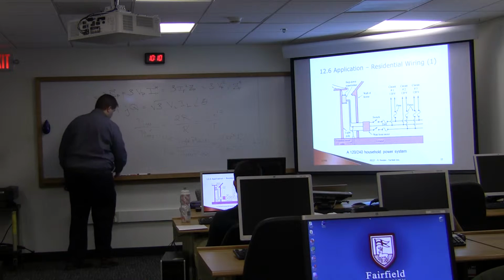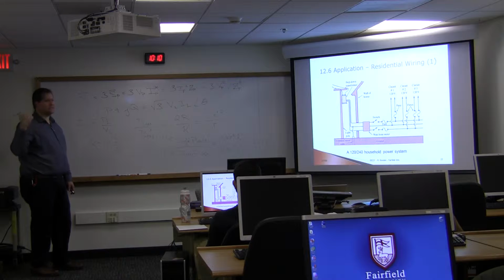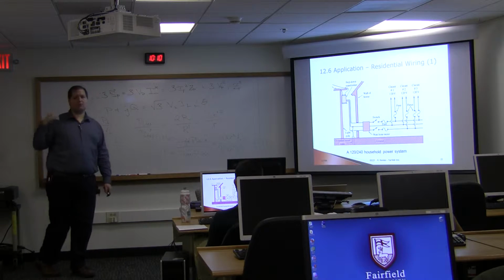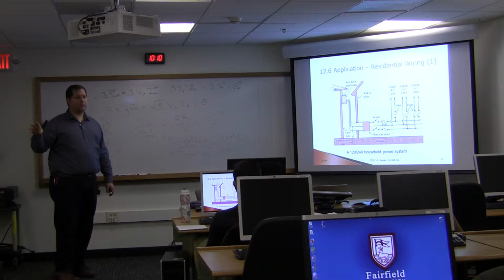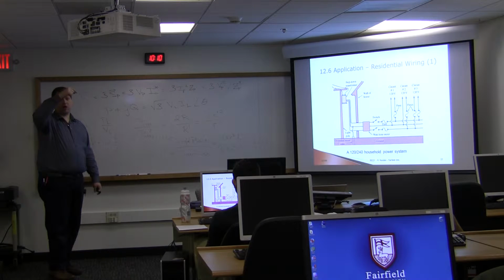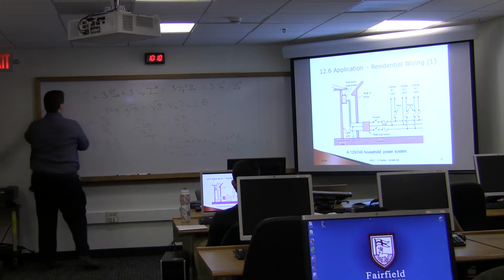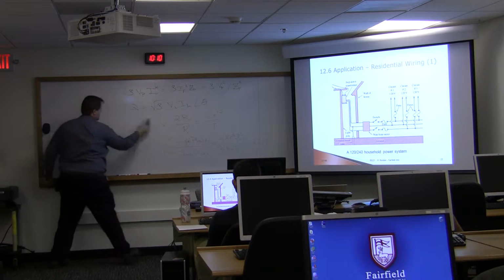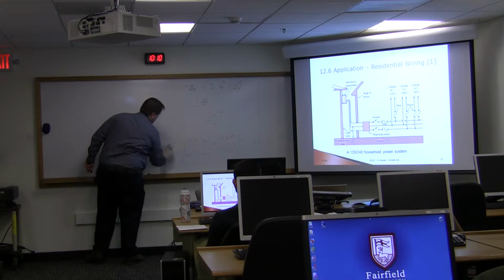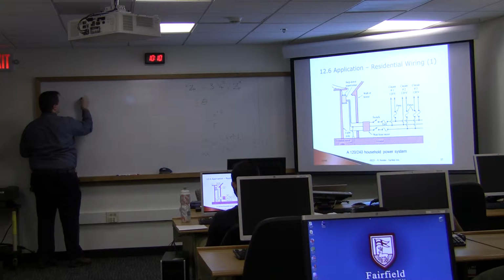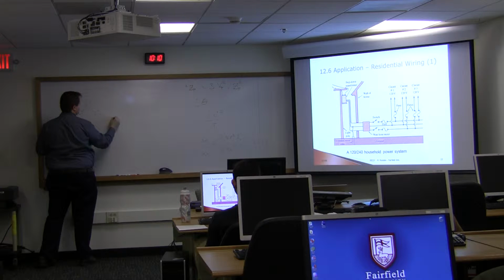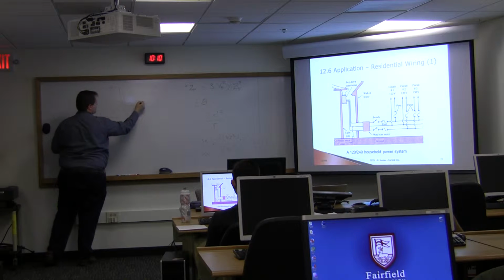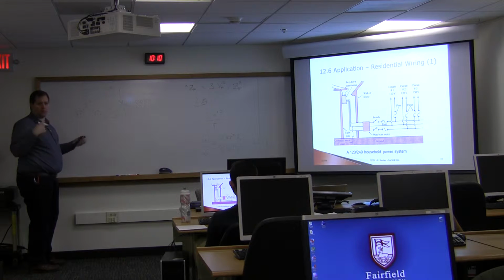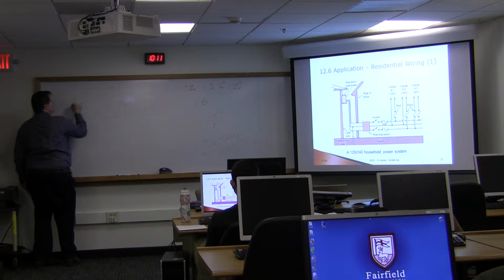When we looked at our systems here, like if we use three-phase in the building, the most common three-phase to have at a point of use is 208 three-phase, meaning it's 208 volts across the line. So that means what we measure across this point to get the VL, and this is 208 volts because of that square root of 3 factor that comes into play when each of these single phases is 120 volts.